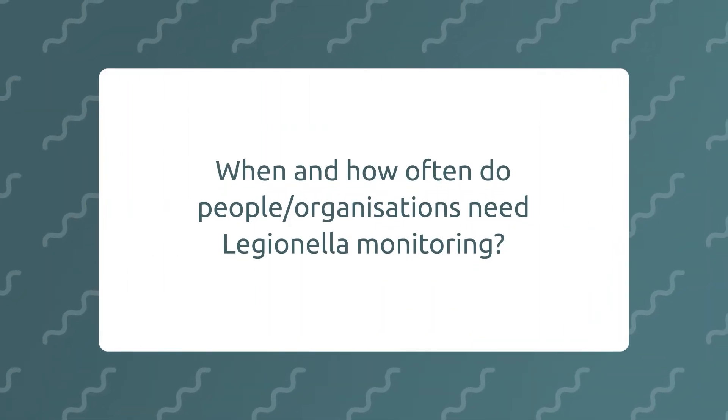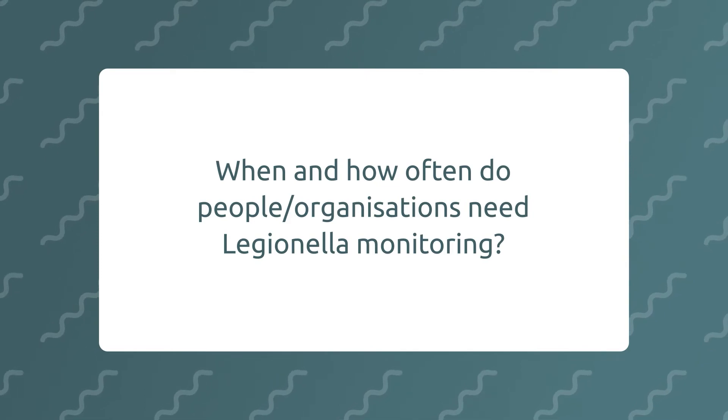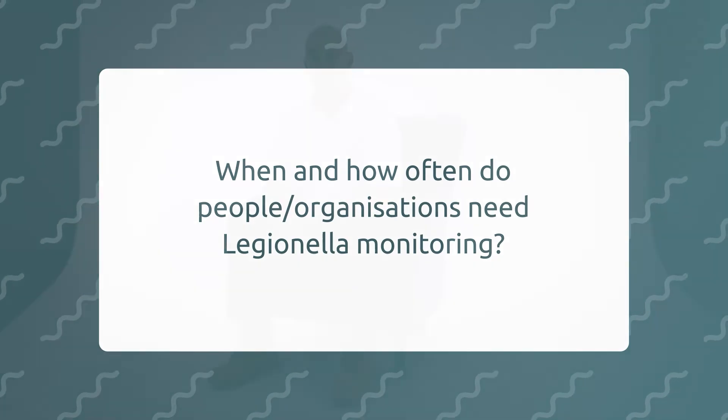When and how often do people or organisations need Legionella monitoring? Monitoring monthly as a rule — temperature checks and sampling monthly. If you are going to have your tanks cleaned and your calorifiers inspected, six monthly to a year.